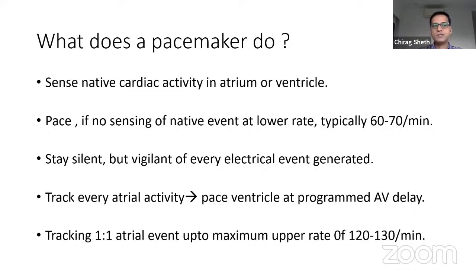The same thing happens for the ventricle also. If it does not sense a native ventricular event, then it will give an impulse to the ventricle at a lower rate. That lower rate is usually programmed by us, typically between 60 and 70 beats per minute. So if it senses native cardiac activity, it remains silent, but it remains vigilant of every electrical event generated. Meaning, if you have it programmed at, let us say, 70 beats per minute, and it does not get the next impulse at the stipulated rate, it will keep on giving another impulse.